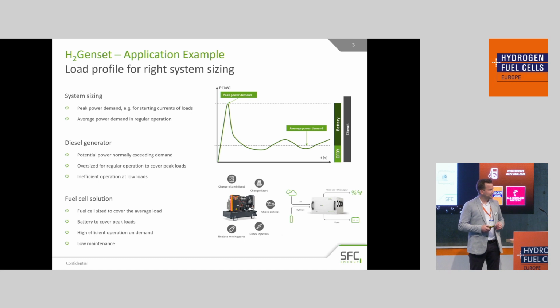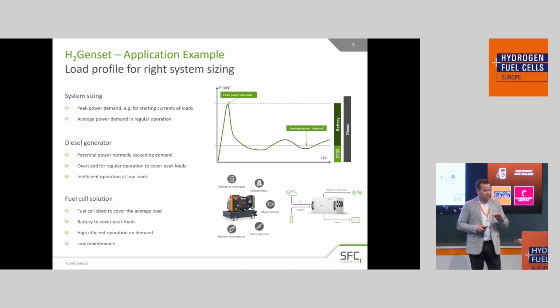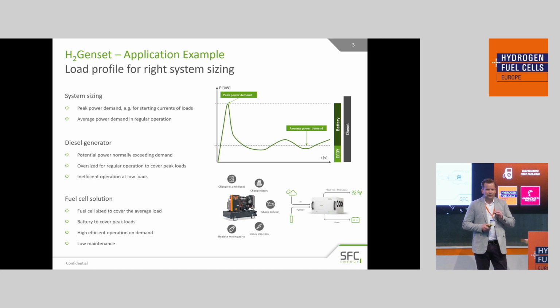What we usually see is these diesel generators are sized by summing up the expected loads, then adding a certain safety factor, which gives the size of the diesel generator. With a hydrogen fuel cell, you have the possibility to directly fit a solution to your demand, meaning you cover the average load with the hydrogen fuel cell, and only the peaks are supplied by battery systems integrated into the fuel cell solution. This way, you can have very efficient operation tailored to your specific demand on site.